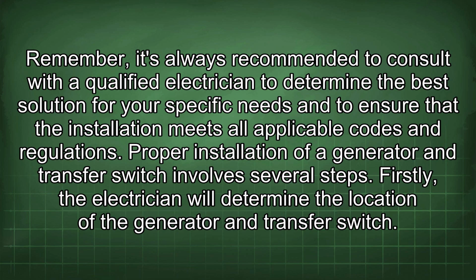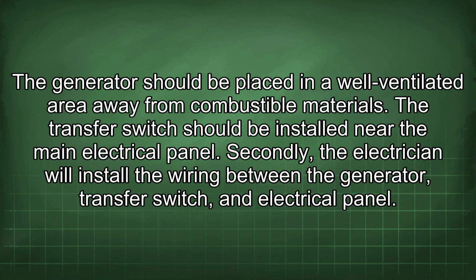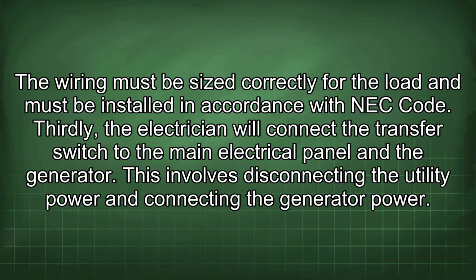Proper installation of a generator and transfer switch involves several steps. Firstly, the electrician will determine the location of the generator and transfer switch. The generator should be placed in a well-ventilated area away from combustible materials. The transfer switch should be installed near the main electrical panel. Secondly, the electrician will install the wiring between the generator, transfer switch, and electrical panel. The wiring must be sized correctly for the load and must be installed in accordance with NEC Code.